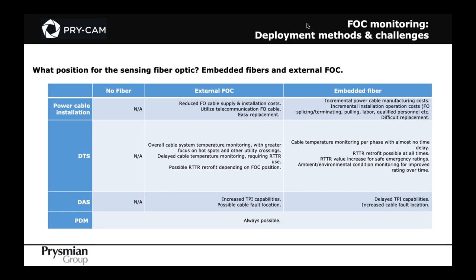Using embedded fibers, DTS allows us to provide and get cable temperature monitoring per phase with almost no time delay. Retrofitting RTTR is possible at all times, and we can increase the value of RTTR by improving rating over time, learning ambient and environmental conditions for our power cables.